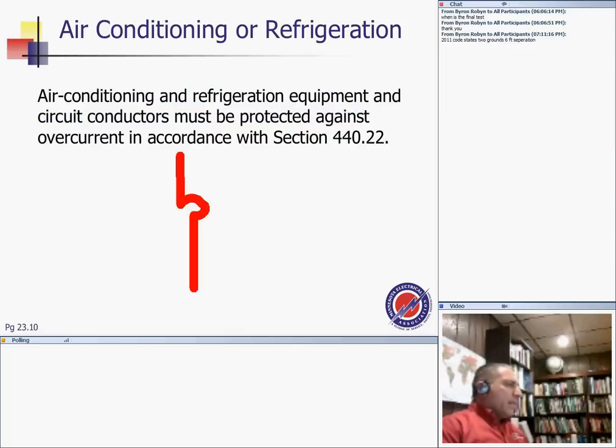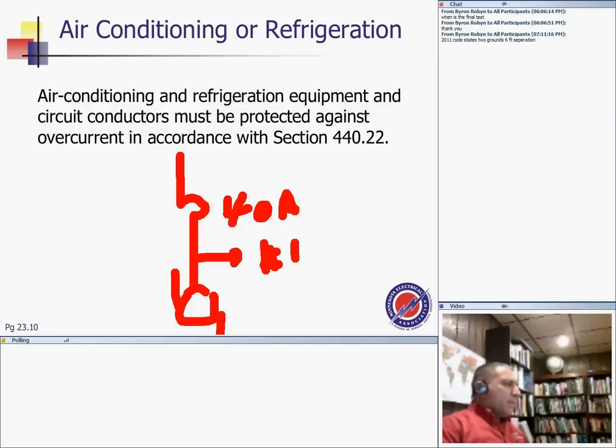Here's an overcurrent device. Here's a 40 amp here, connected to a motor, a machine that has a motor, and the conductor here is number 14. Seen something like this? A 40 amp circuit breaker feeding number 14. Anybody seen that? So something like this, a lot of people go nuts. Are you kidding me? Number 14 is rated for 15 amps. How would you put a 40 amps on it? The reason for this, guys, is okay on motors because motors have an overload protection.